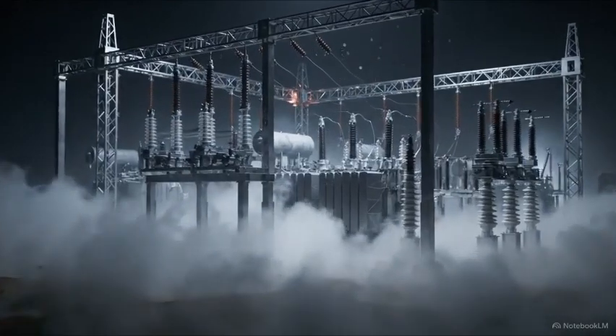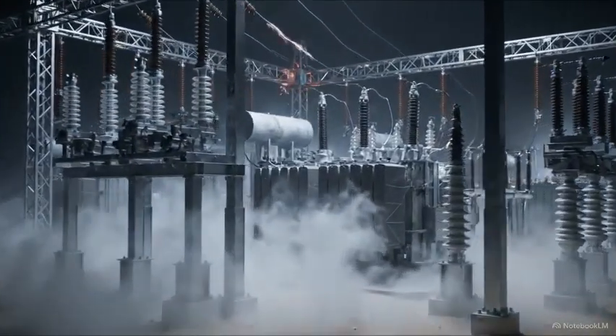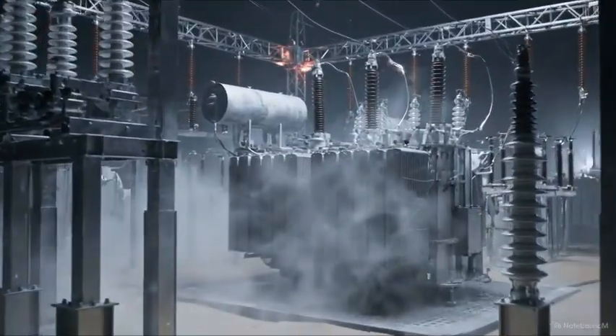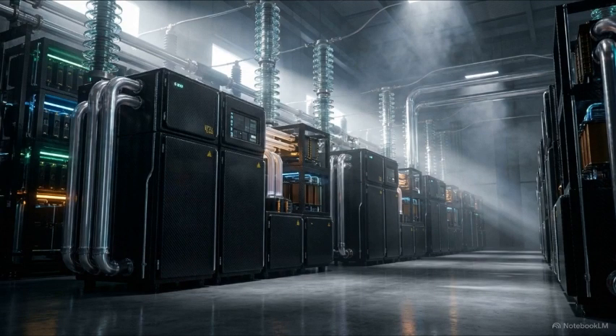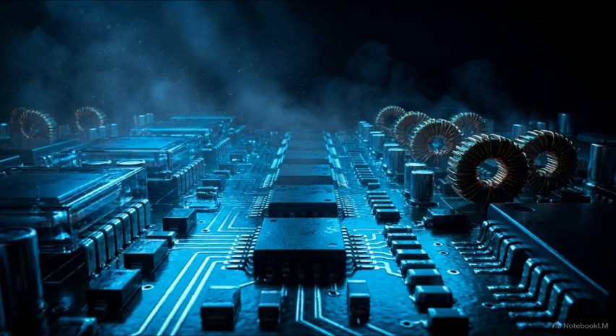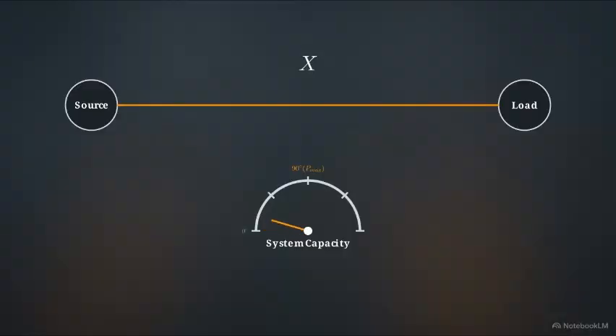But the most powerful intervention happens exactly halfway between the power plant and the city. At this location, engineers install a flexible AC transmission system, or FACTS device. Packed with high-speed power electronics, it dynamically injects or absorbs reactive power from the grid to lock the voltage at this exact midpoint perfectly rigid.